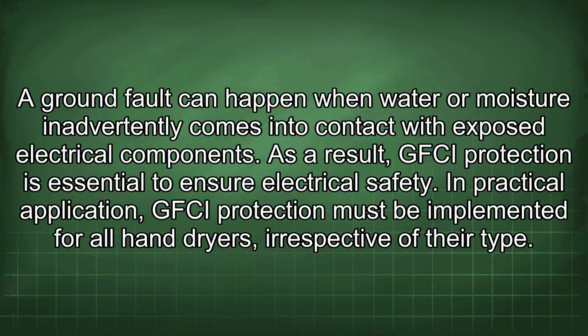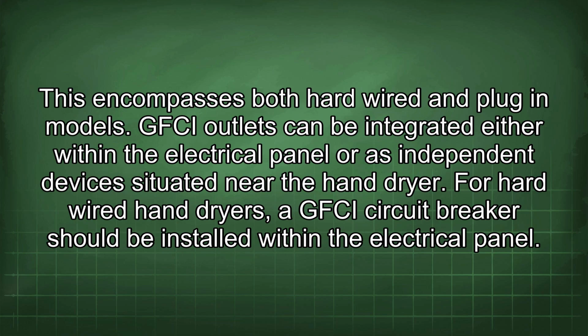In practical application, GFCI protection must be implemented for all hand dryers, irrespective of their type. This encompasses both hardwired and plug-in models. GFCI outlets can be integrated either within the electrical panel or as independent devices situated near the hand dryer. For hardwired hand dryers, a GFCI circuit breaker should be installed within the electrical panel.